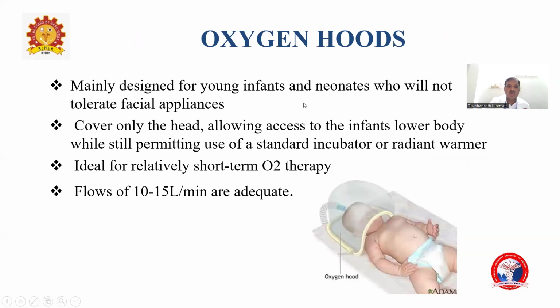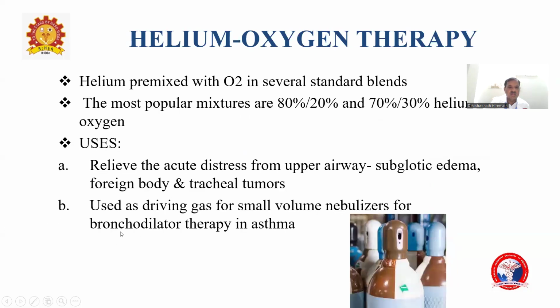Oxygen hoods are mainly used for young infants who will not tolerate facial appliances. Only the head is enclosed, allowing access to the lower body while still permitting the use of a standard incubator or radiant warmer. It is ideal for relatively short-term oxygen therapy, with a flow rate of 10 to 15 liters per minute.